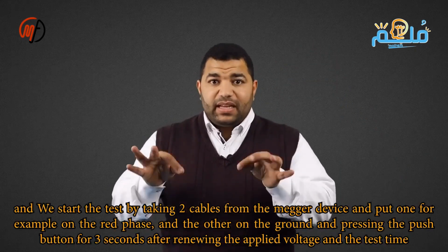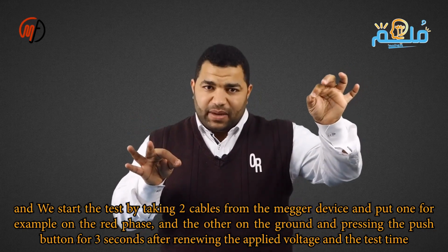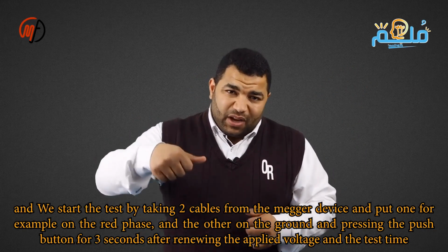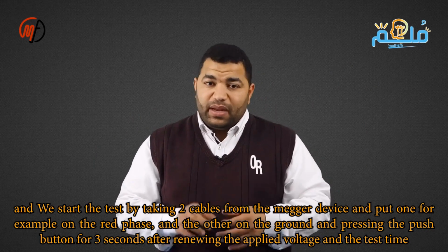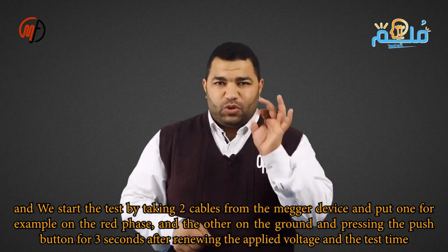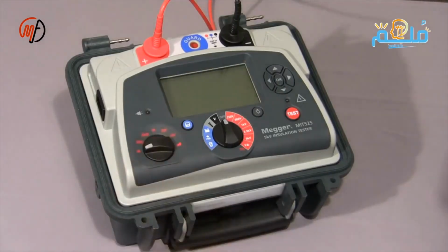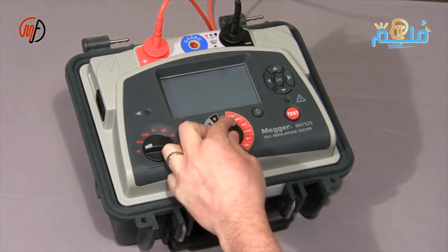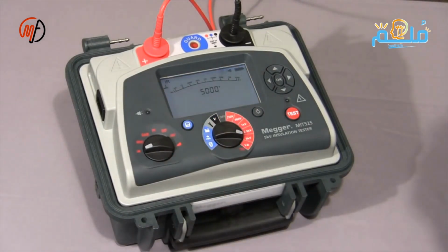We start the test by taking 2 cables from the Megger device, placing one on the red phase, for example, and the other on the ground. We press the push button for 3 seconds after setting the applied voltage and the test duration. It's important to set the applied voltage and test duration correctly. It's more advisable in general to ground the other phases.